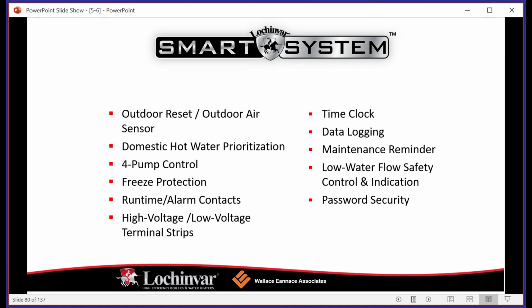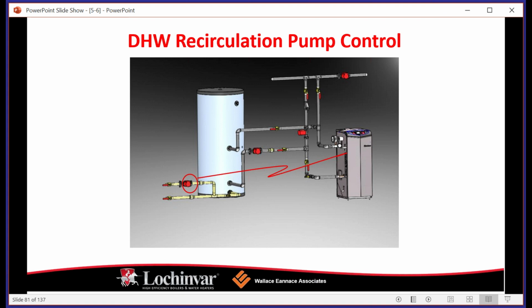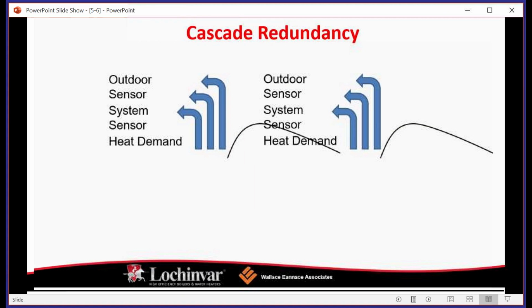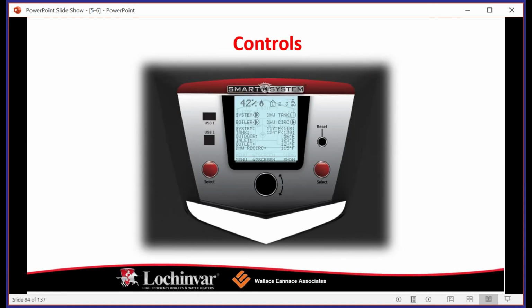So the smart system is going to allow us to set up the boiler. We're going to do our method of control. You can do domestic hot water priority. You can run freeze protection, alarm contacts, clock, data logging, safety controls and indications. All of them are password protected. Nice thing about the password protection is that you get the same password across all the product lines. So you don't have to remember like 10 different passwords. It's all the same password. Now, let's touch on that outdoor reset outdoor air sensor. It's available through here. Let's see if I have one, and we'll come back to it.